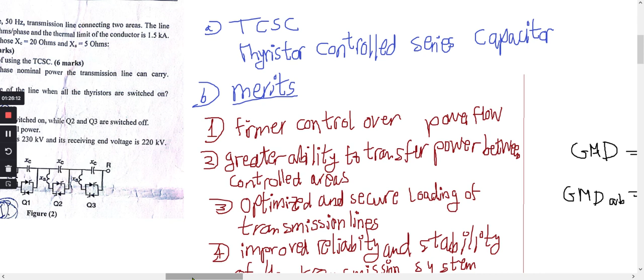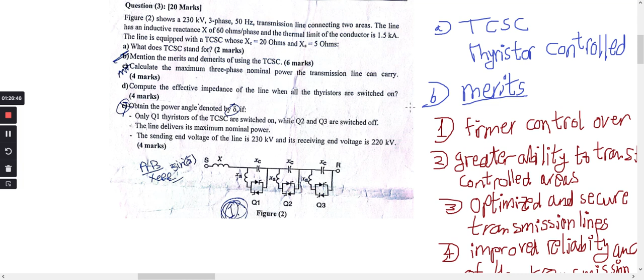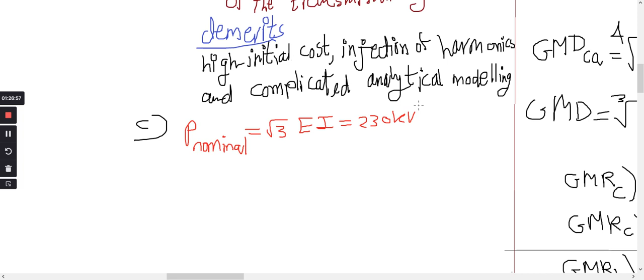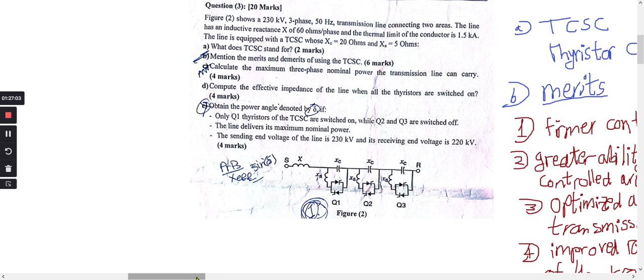Okay. Maximum three-phase nominal power the transmission line can carry. So P nominal equals square root 3 times E times I. What is E here? It's 230 kilovolts, times 1.5 kilo amperes.